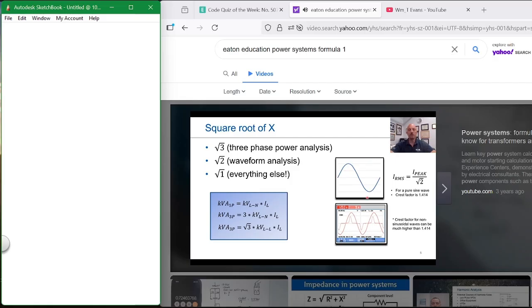When does the square root of 2 come into play? That really comes into play when we're talking about the RMS versus peak. Now, if you look at the peak and you compare that to the RMS, which is more of an average value, it's typically off by the square root of 2 when you have a very nice sinusoidal waveform. Where that doesn't happen is when you have harmonics, like the bottom picture, where the current has a crest factor, or a peak over the RMS, of maybe 3, or a number considerably higher than the square root of 2. So the square root of 2 comes into play for those kinds of things, and as a consultant, you might not run into that as much unless you're dealing with waveforms and harmonics and things like that.